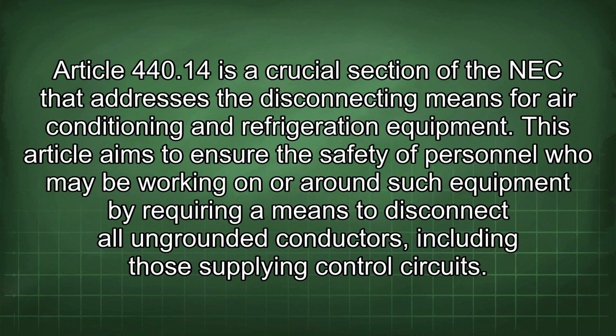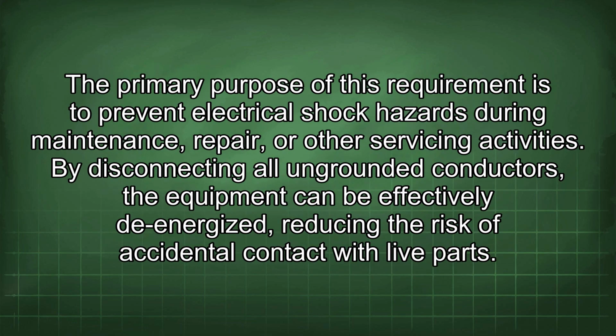Article 440.14 is a crucial section of the NEC that addresses the disconnecting means for air conditioning and refrigeration equipment. This article aims to ensure the safety of personnel who may be working on or around such equipment by requiring a means to disconnect all ungrounded conductors, including those supplying control circuits. The primary purpose of this requirement is to prevent electrical shock hazards during maintenance, repair, or other servicing activities. By disconnecting all ungrounded conductors, the equipment can be effectively de-energized, reducing the risk of accidental contact with live parts.